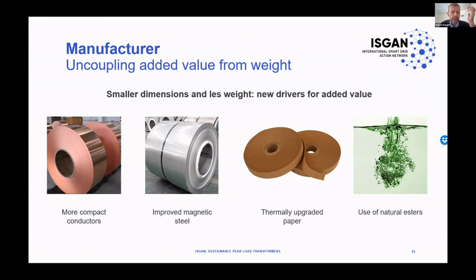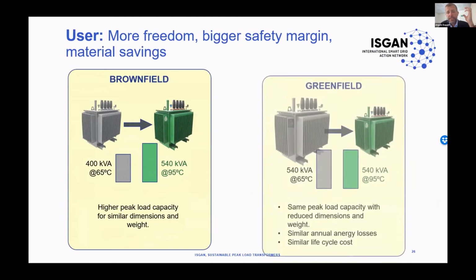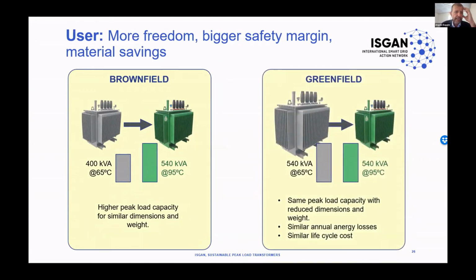The next one, the customer perspective, the user perspective, more or less the same benefit as for the manufacturer, adding that higher peak load capacity for similar dimensions allows us to increase the power in case of brownfield for the same dimensions, and for greenfield we can improve the energy performance. At the end, in one word, in my opinion, we need material efficiency to remove the rigidity we have now in case of our transformer, to multiply the opportunity to reach sustainability considering the usage of the transformer.